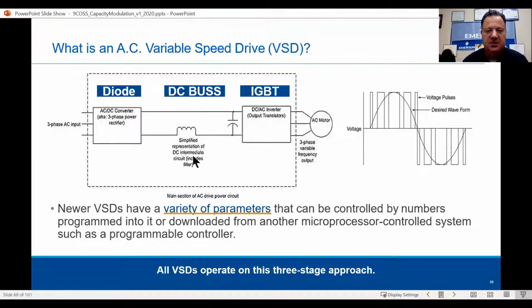Simplified representation of DC intermediate circuit includes the filter. So again, we're filtering that, keeping it stable, all right? Cleaning it up, if you will. And that helps prevent the inrush current coming in from the diodes. And then we've got the IGBT, which is nothing more than insulated gate bipolar transistors. And we're manipulating those switches again to make it look like it's AC. It's an AC motor, three-phase variable frequency output. And you can see here the voltage pulse, the desired waveform. Again, the faster we're making those switches go on and off, the smaller that wave's going to be here on this.